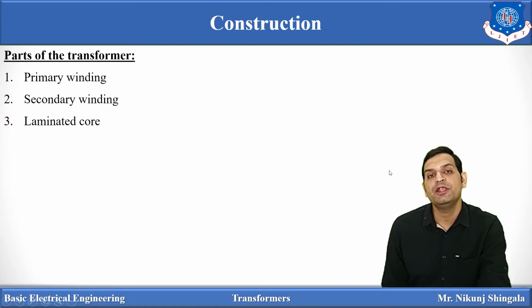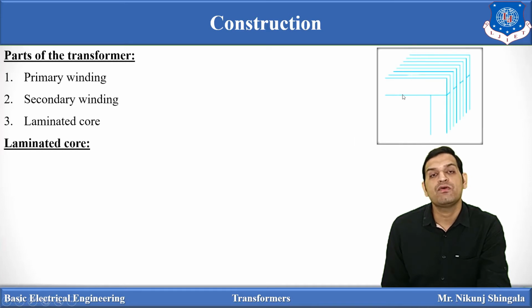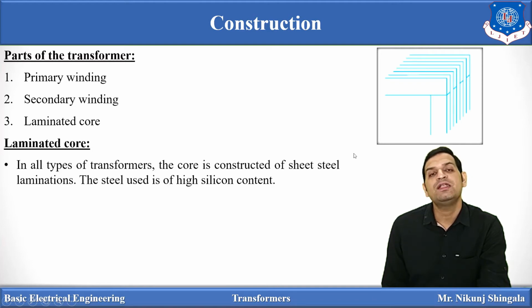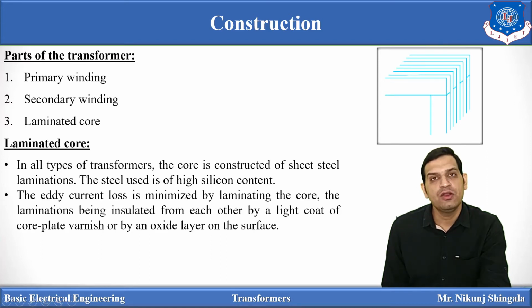Now what about the laminated core? The core is not a single piece, but is made up of thin lamination sheets. Here you can see it consists of a number of lamination sheets. In all types of transformer, the core is constructed of laminated sheet steel. The steel used has a high silicon content. The eddy current loss is minimized by laminating the core, so each lamination is given insulation. The laminations are insulated from each other by means of an oxidation layer, a light coating.